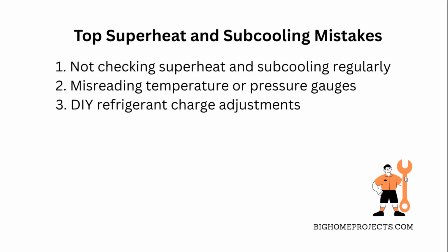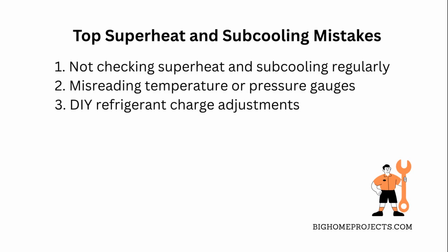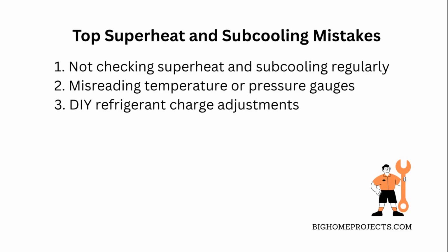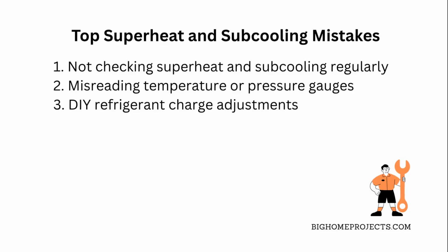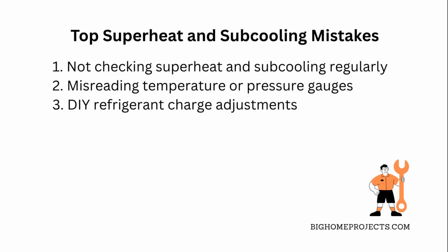One of the biggest mistakes people make with superheat and subcooling is not checking them regularly, which leads to inefficient cooling and higher electric bills. Another common issue is misreading the temperature or pressure gauges, so make sure your tools are calibrated and you know what normal ranges look like for your system.